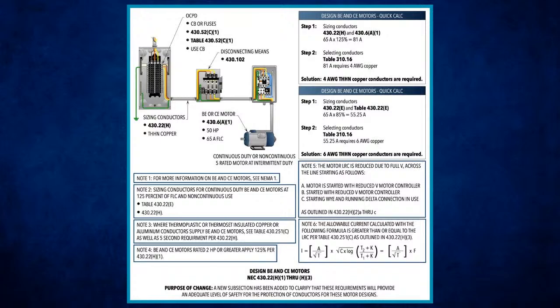Okay, so you've got all these parts that you need to look at at this point. Now, since I've started right there, what do I want to do next? That is the question. Since we're doing a motor, you would start at Part 1. Go over and look at Article 430 and pick up 430.6(A)(1). Basically, if you're sizing your overcurrent device or your conductors, you're going to use the table values. If you're sizing your overload protection, you're going to use the nameplate, and that'll be in 430.6(A)(2).